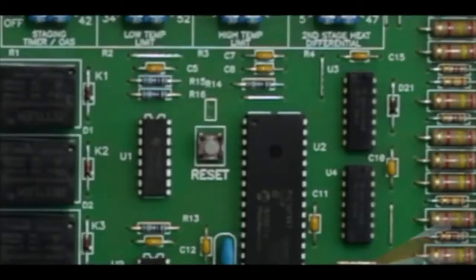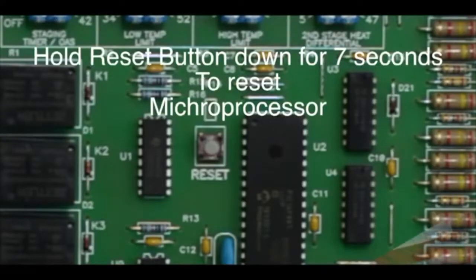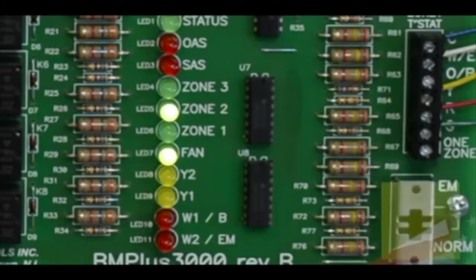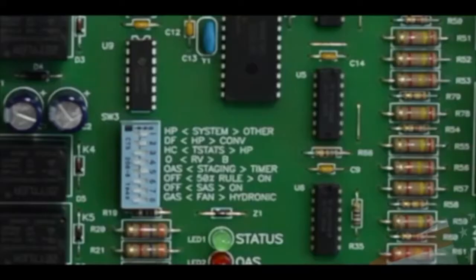The reset button clears the built-in timers for the board, allowing for faster system commissioning and startup. Holding down for 7 seconds resets the CPU for the entire zone system. An emergency heat switch is located on the board for energizing emergency heat when using heat-cool thermostats in heat pump applications. You can also use the switch to override the dual fuel system to second stage, overriding the outside air sensor. The dip switches give you options for system operation.